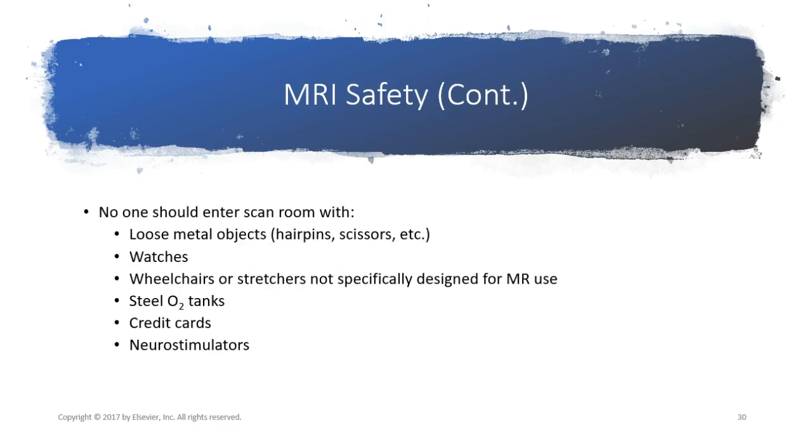No one should enter the scan room with loose metal objects. Hairpins, they will rip right out of your hair with the hair still in it and be in the magnet. Scissors, pins, watches. If you go in with your watch on, it will stop working. And if it's a digital watch, then you just need to replace your battery, and it'll work a few times going in and out of the scan room, but not long term.